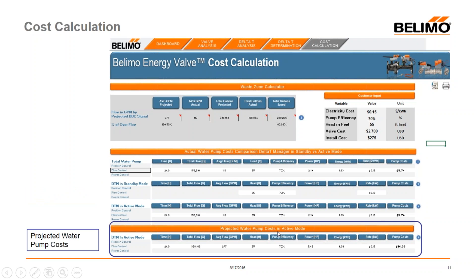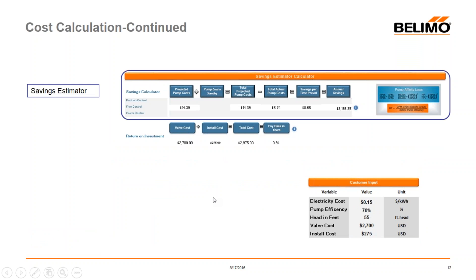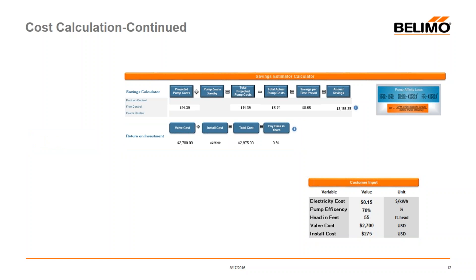At the bottom is the projected pump water costs section, which takes the information from above and calculates what the value would have been without delta T manager control. The savings calculator compares pumping costs in standby versus active mode with the total projected pumping costs, subtracts out what the actual cost was, and gives you a savings per time period and an annual savings. Below that is the return on investment, which takes the cost of the valve and installation divided by the annual savings to give you the payback in years — using basic pump affinity laws, nothing more.